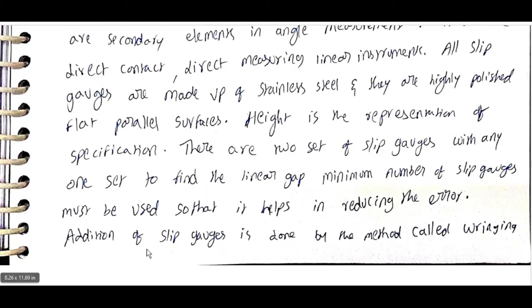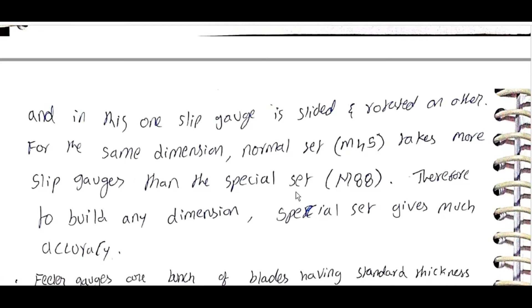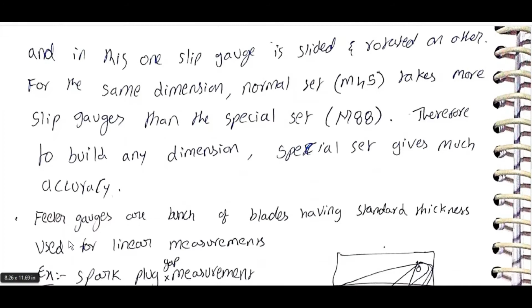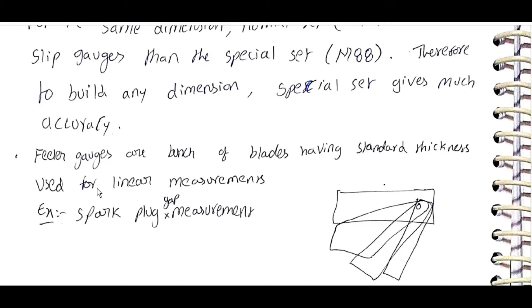Addition of slip gauges is done by the method called wringing, in which one slip gauge is slid and rotated on another of the same dimension. The normal set M45 takes more slip gauges than the special set M88. Therefore, to build any dimension, the special set gives much more accuracy. Feeler gauges are a bunch of blades having standard thickness, used for linear measurement. Example: spark plug gap measurement.